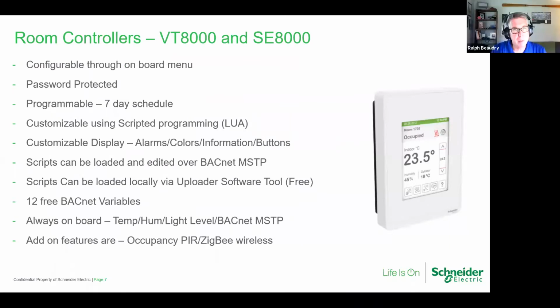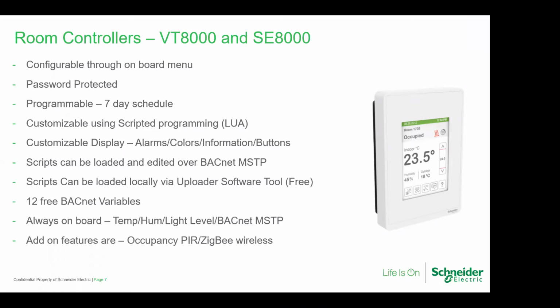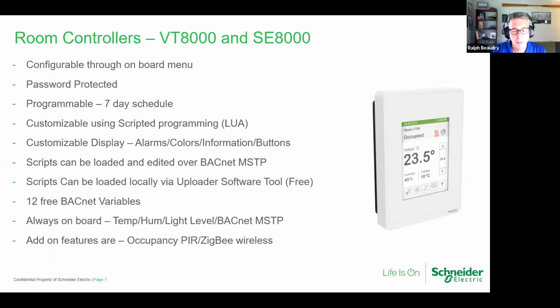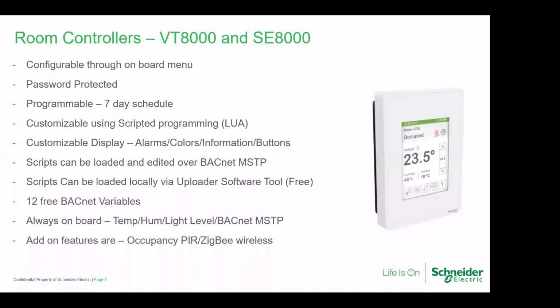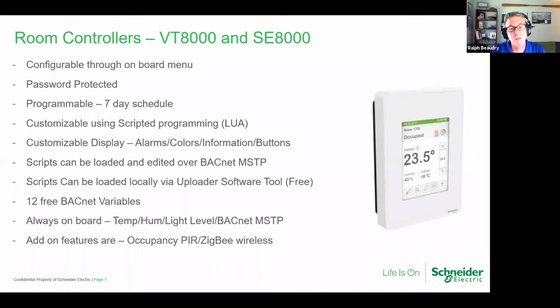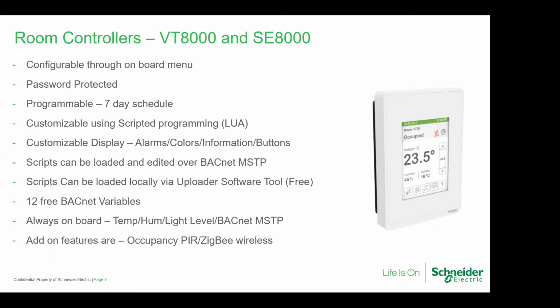So it's a configurable device with an onboard menu. The menus can be password protected. It's always programmable, 7-day schedule programmable. You can customize it, so you can take the base application - for instance, package rooftop. It comes in 2 heat, 2 cool as our standard application. But sometimes we run into 4 stages of cooling in a package rooftop unit. We can do 4 stages of cooling by adding a little bit of custom scripting into the 8000, using a programming language called Lua. It's an open source programming language.